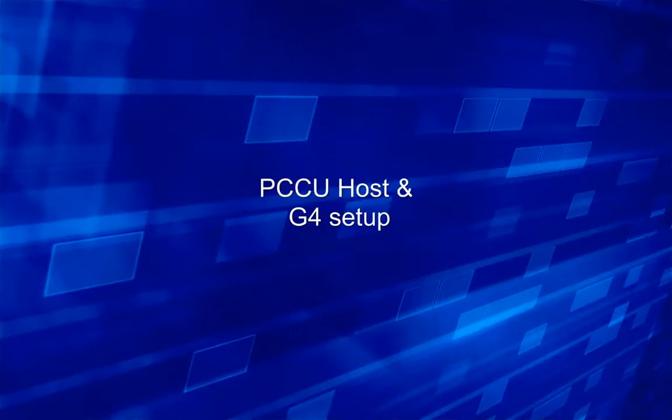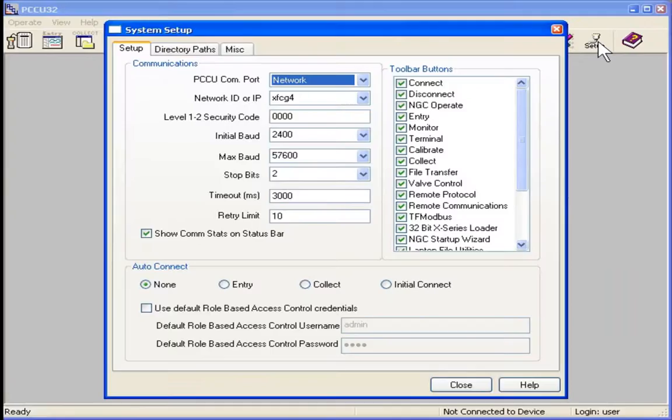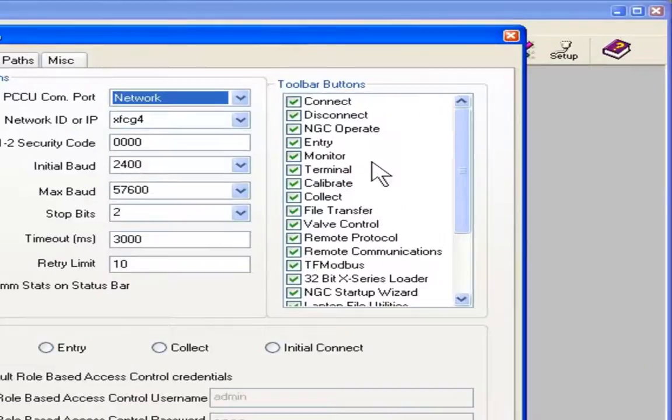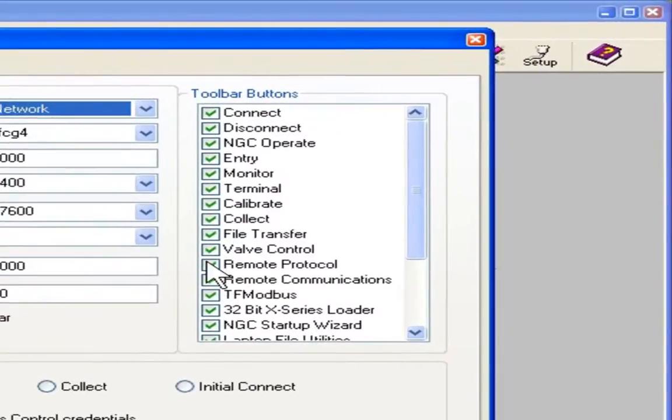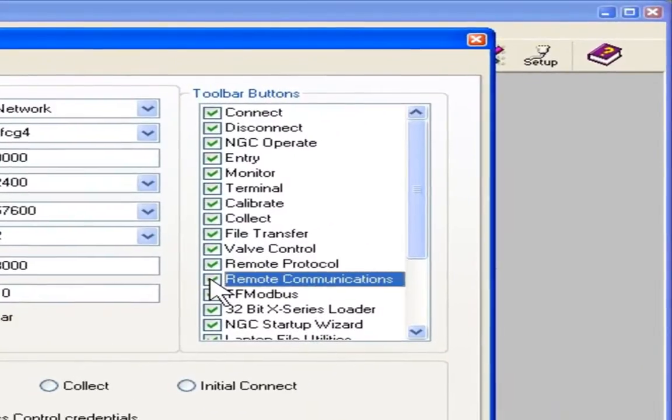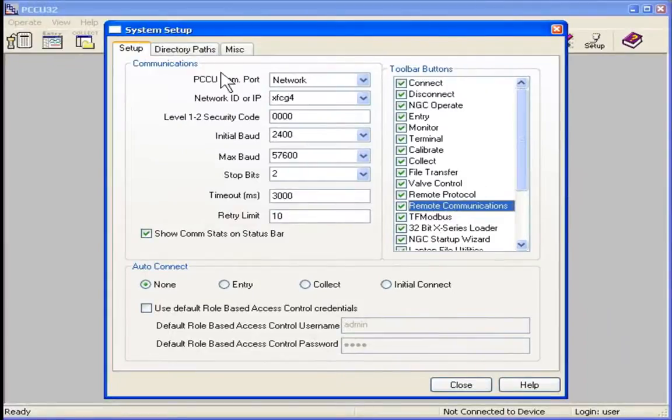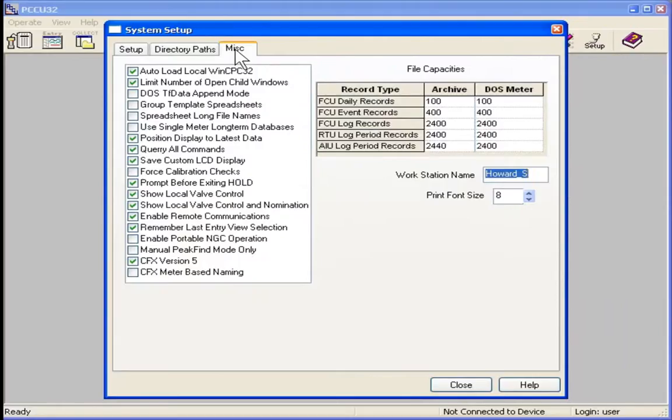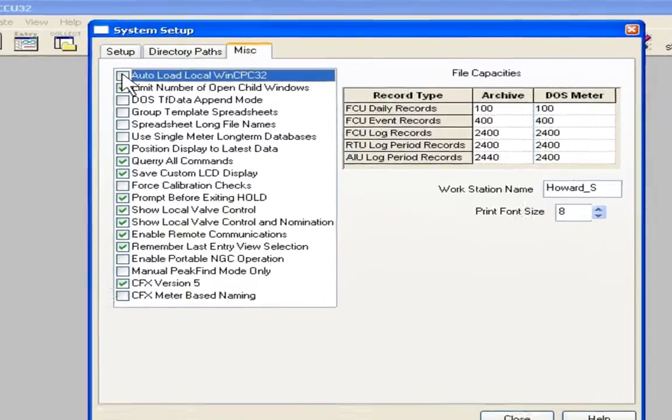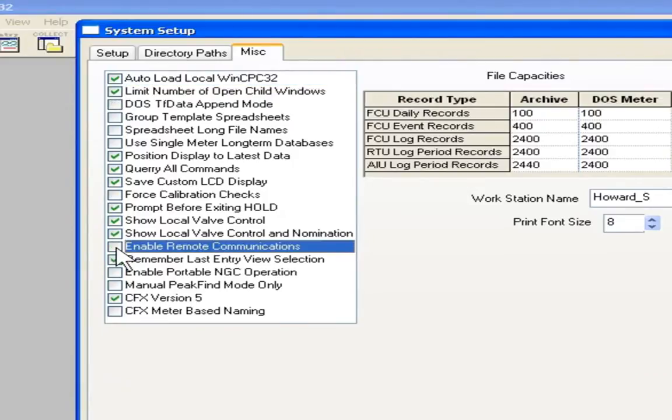Let's first look at some general setup in PCCU for remote communications. We will go to the setup tab, and we will select setup, and we will want to check remote communications as you can see here. Then we will need to move to the miscellaneous tab. We will need to check auto load local CPC, and also check enable remote communications.